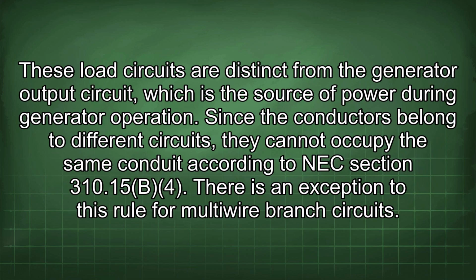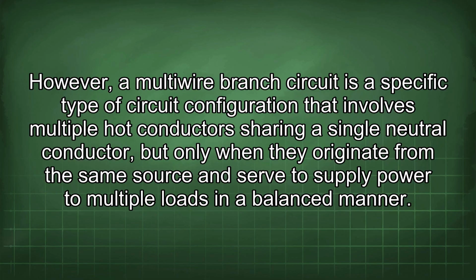These load circuits are distinct from the generator output circuit, which is the source of power during generator operation. Since the conductors belong to different circuits, they cannot occupy the same conduit according to NEC Section 310.15b. There is an exception to this rule for multi-wire branch circuits. However, a multi-wire branch circuit is a specific type of circuit configuration that involves multiple hot conductors sharing a single neutral conductor, but only when they originate from the same source and serve to supply power to multiple loads in a balanced manner.